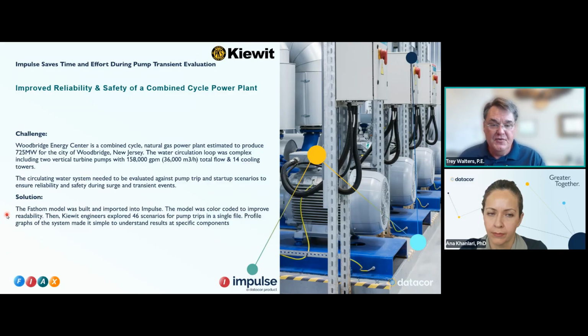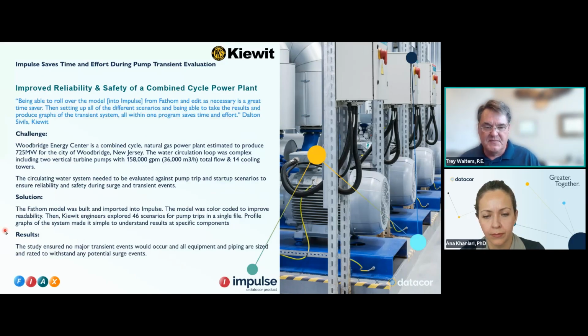The solution is they first built a Fathom model, a steady state. Then they were able to take that entire Fathom model and port it completely into Impulse with all the data in there. And then they had to put in the transient things in Impulse. The model was color coded to improve readability. Then they explored 46 scenarios for pump trips, all in a single model file. They did profile graphs of the system, which made it simple to understand result-specific components. So results were: the study ensured no major transient events would occur, and all equipment and piping are sized and rated to withstand any potential surge events.